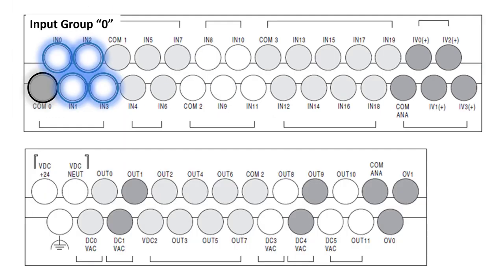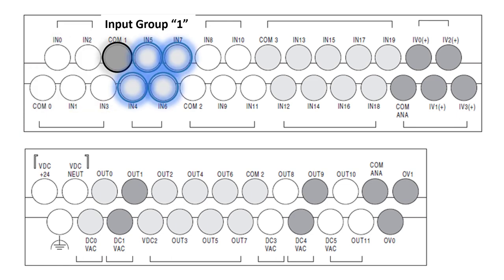So let's talk about the first group of inputs, COM0, input 0, 1, 2, 3. These five terminals, so to speak, are isolated electrically from all the other terminals on this input strip, which means that if you want to use 12 volts DC for input 0, 1, 2, and 3, you could do that, and then you have a common 0 that would return to the 0 volt DC side of the power supply. Now, either way, you're probably going to jumper all the commons together, because typically you don't leave anything floating in your system.